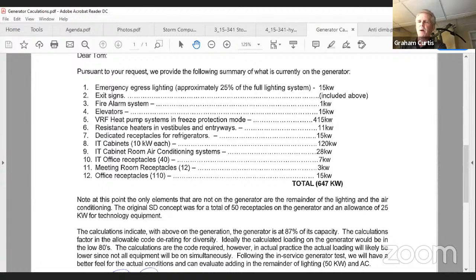So the question came up: could we add more things to the generator? Well, the calculations are somewhat conservative, and the actual load, because you're not going to be loading up all these receptacles, not going to be running the air conditioning units and the heat pump. It's a very variable load, and you'll unlikely see that, but they move the heat around. So it's not an exact science. They only see that load on a very cold day. And once you start up the load, there's an initial startup, but after you're running, the load comes down. So you have more capacity.